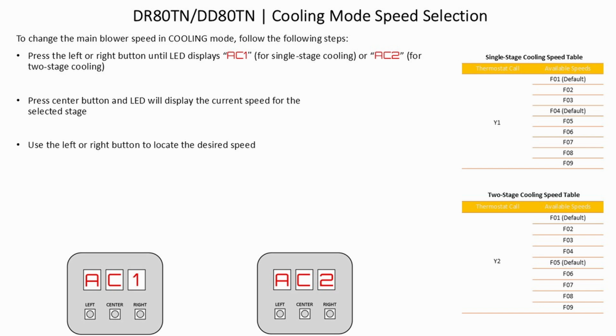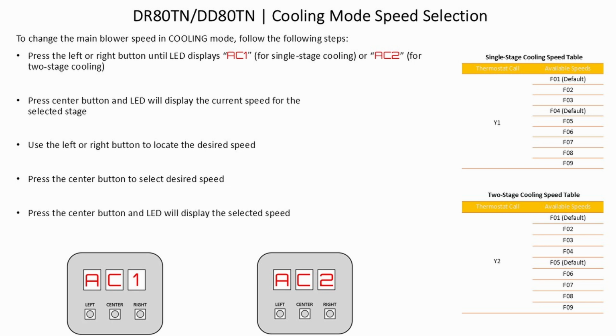Use the left or right button to locate the desired speed. Press the center button to select the desired speed. Press the center button again and the LED will display the selected speed. All 9 speeds are available for both single and two-stage cooling. Single-stage cooling, Y1, F01, and F04 are default. For two-stage cooling, Y2, F01, and F05 are default.